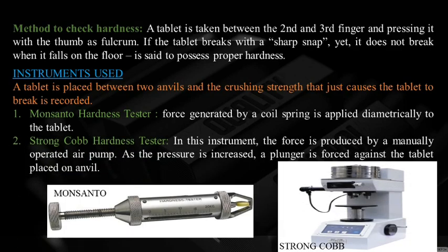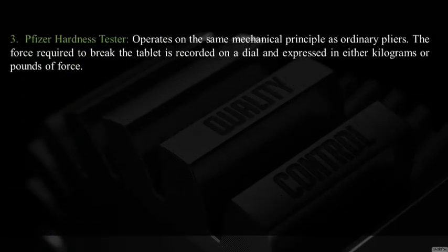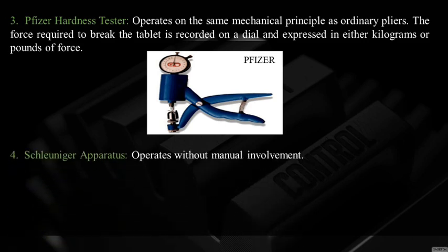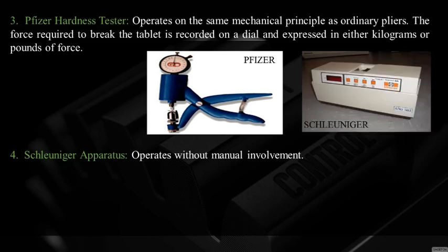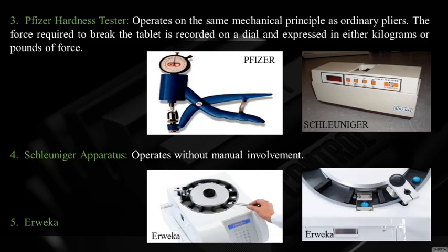The Strong Cobb hardness tester applies force using a manually operated air pump; as pressure increases, a plunger is forced against the tablet on the anvil. The Pfizer hardness tester operates on the same mechanical principle as ordinary pliers, and the force required to break the tablet is recorded on a dial expressed in kilograms or pounds of force. The Schleuniger hardness tester operates without manual involvement — you press the on button, place the tablet between the plungers, and it displays the force required to break the tablet. Another instrument is the Erweka tester.